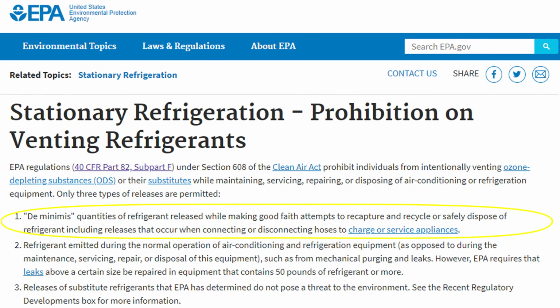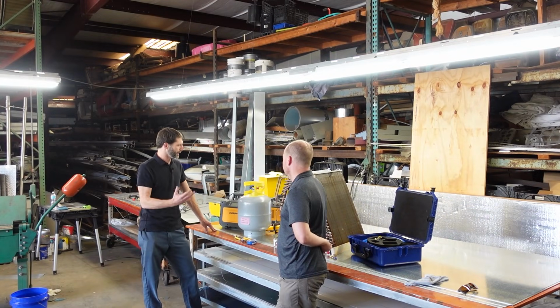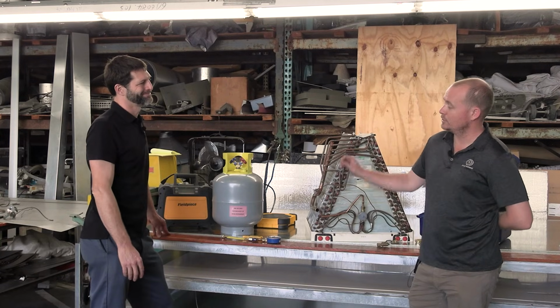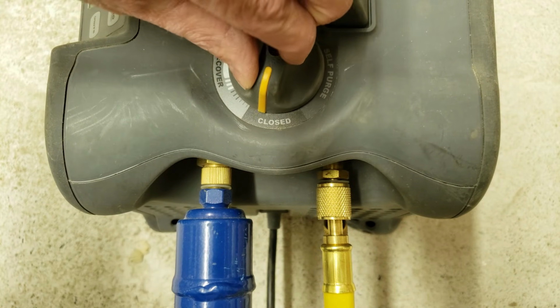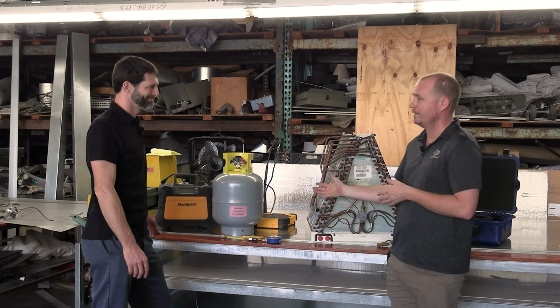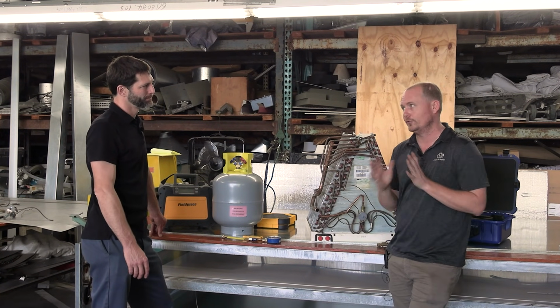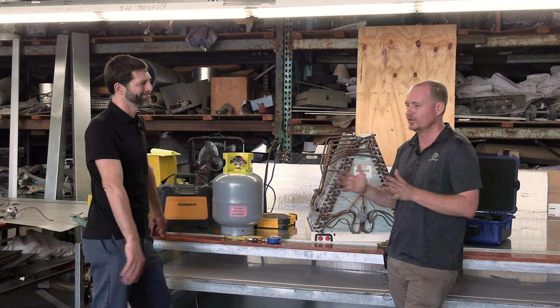We don't want to vent refrigerant, but we've done our absolute best to get all the refrigerant out of the system and into that recovery bottle so we don't end up venting it into the atmosphere. Yep. Some machines have a purge mode, so you're purging the refrigerant out of the condenser. It kind of repipes everything, so you don't have that. But all of that has been reviewed by the EPA. It's not like the EPA doesn't know how these things are made.